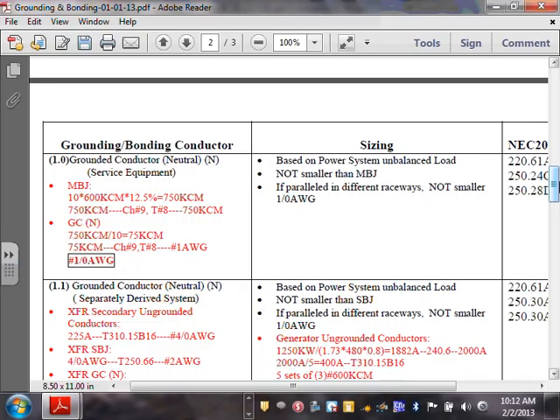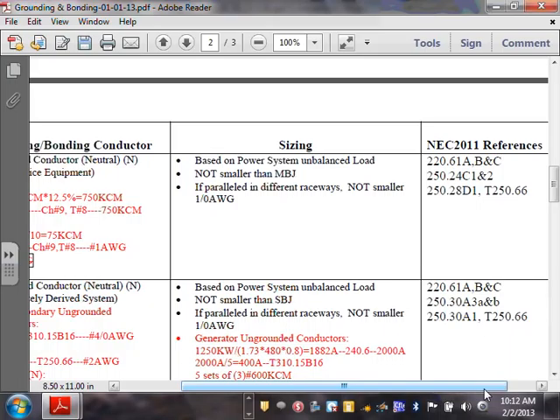And because I know you guys are creative and you're going to accuse me of getting things from my basement, like I said, here's where it tells you in the code. And please don't make me go verify each one of them. You guys go verify at your own time. So this is where it tells you where these can summarize all the stuff for you. The most important one is table 250.66 because that's how we size the main bonding jumper.